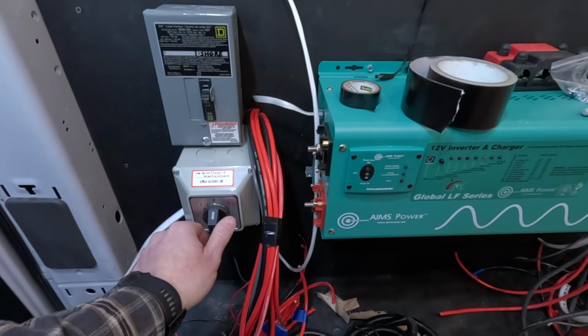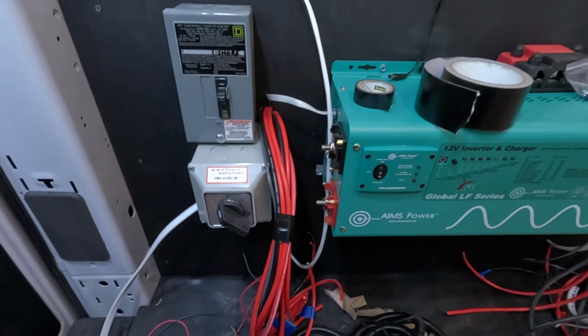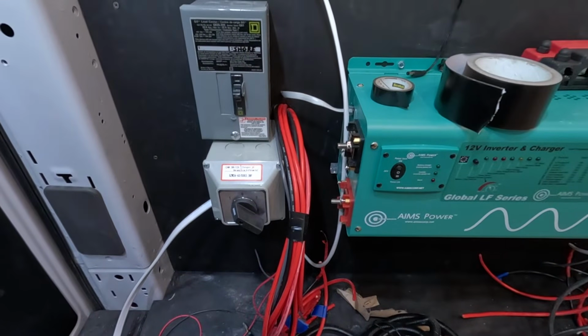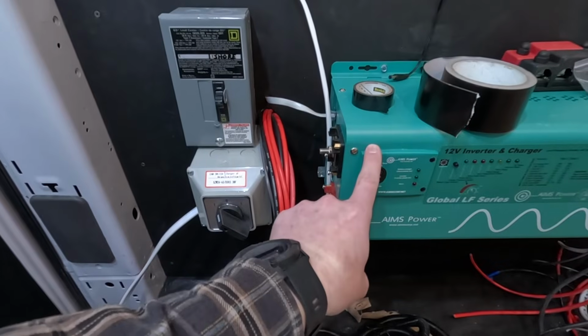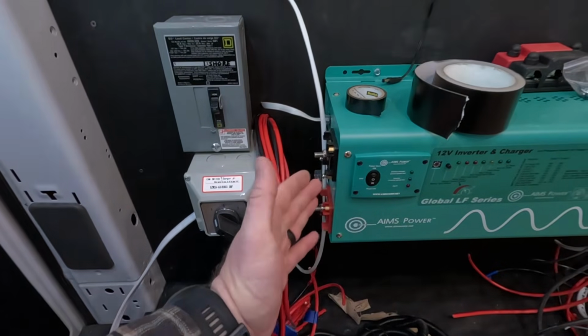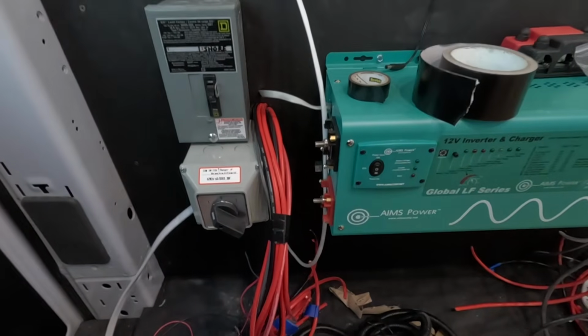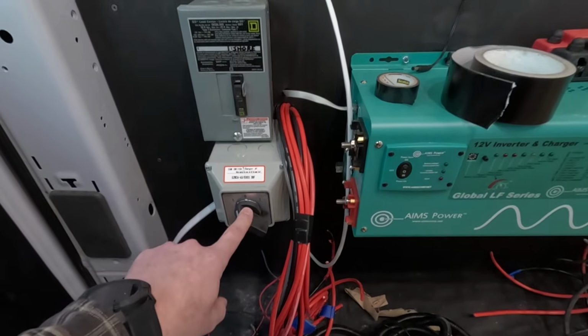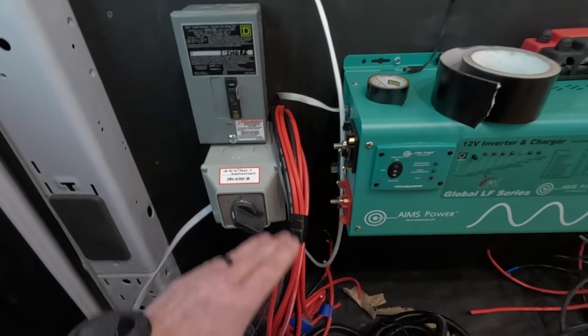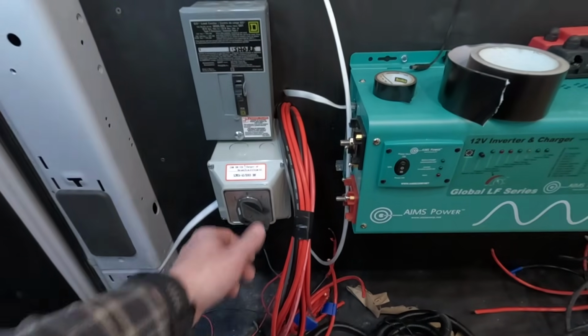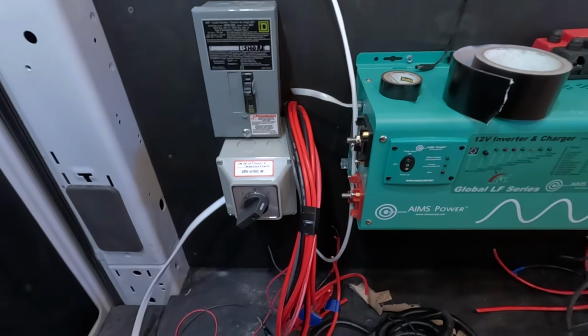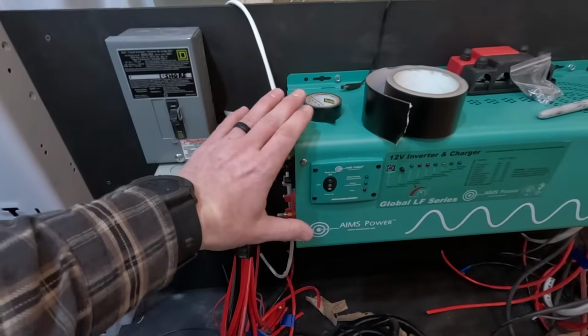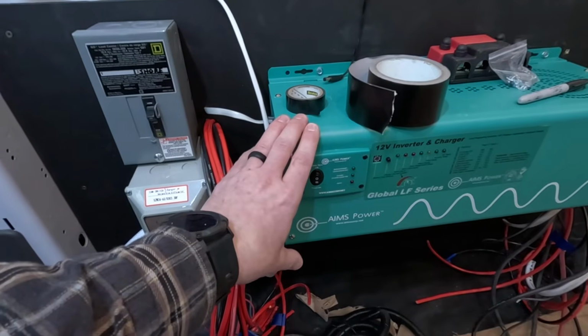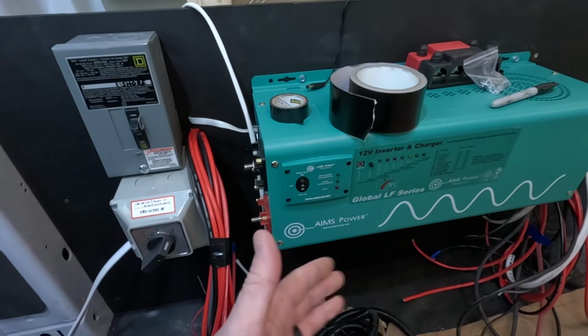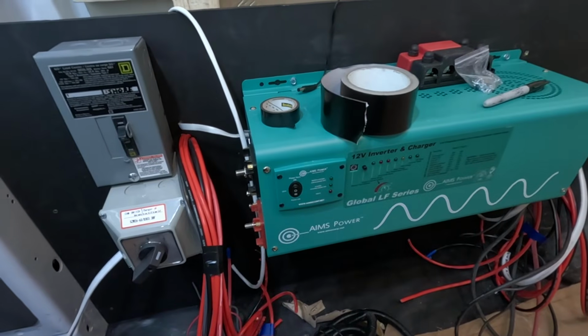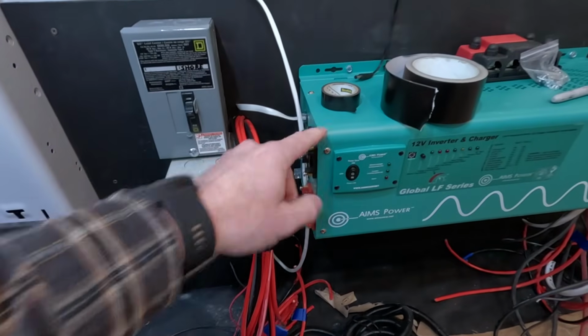If I switch it over to 1, that's called a shore power bypass. So if there's something wrong with the inverter and the transfer switch isn't passing shore power, I can just switch it to 1 and we can still have power, whether it's from a generator, plugged in, or whatever. If I switch it to 2, this will be the mode it's normally in, where it's allowing the inverter to control the shore power, acting as a transfer switch, battery charger, etc. This is just in case there's ever anything wrong with this.